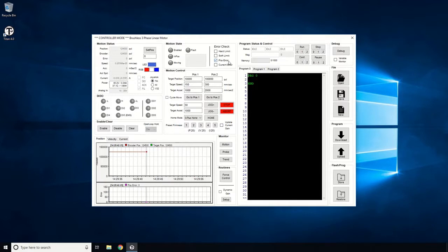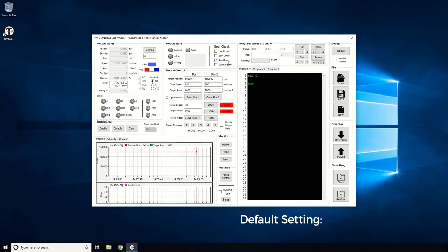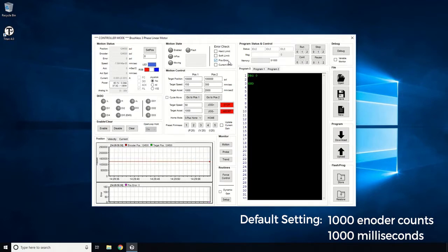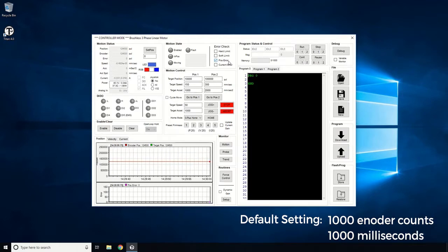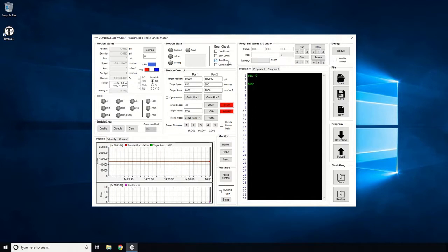Position Error Monitoring will check the position error, and if the error value goes above a certain amount for a defined amount of duration, a fault will occur and motor power will be disabled. The default value should be 1000 encoder counts for 1000 milliseconds. You can update these with different values in the Configuration screen. OK, let's enable the motor using the Enable button.